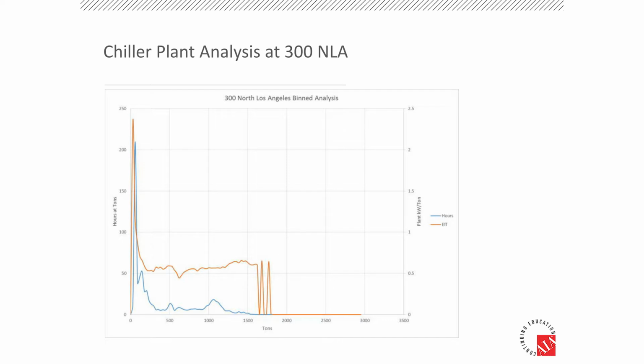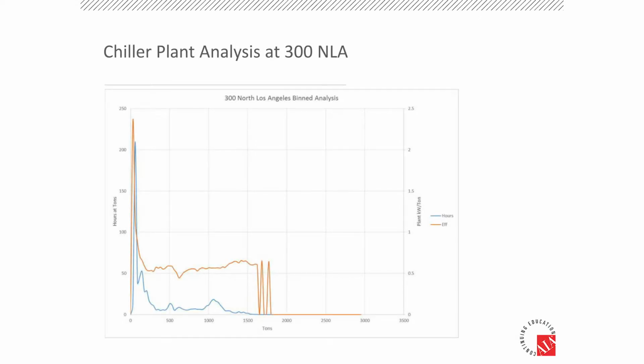All right, so you notice this is just a simple chart of where the plant operates as far as hours versus tonnage. So typically you're designing a plant for maximum capacity, but the biggest thing that design engineers have overlooked all along, or throughout history, has been this low load operation side. In the design engineer's defense, because I used to be one, GSA said the building was unoccupied at this point. Said there is no low load, or we don't have a load below here. The plant will always operate at least 300 tons and never below. And we noticed that the tremendous number of the hours are from 300 tons and down. So that drove the capacity of the machines that we're looking at.